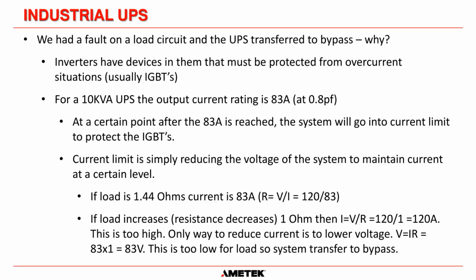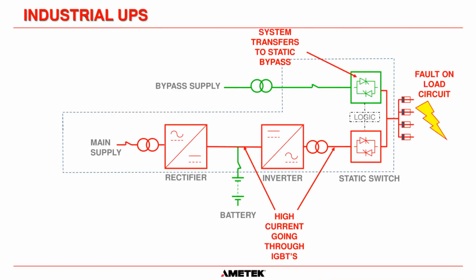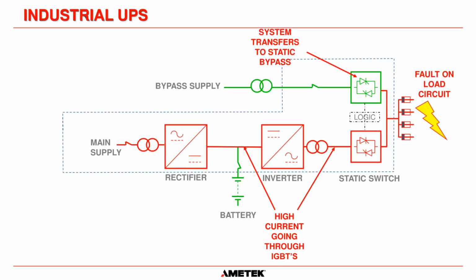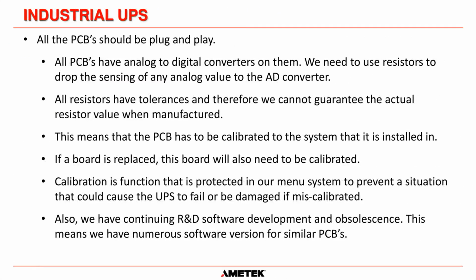So it will do everything it can to stay on inverter and keep the voltage up. But when Ohm's law says it has to go past, let's say, 100 volts AC, the system is going to say, that's too low for my loads, I'm going to transfer to bypass. And that's basically showing you at block diagram level what happens. If there is too high a current going through the IGBTs, then the system is going to transfer to bypass, and then the bypass will clear the loads. The bypass has a huge amount of power behind it, and it will trip the load if necessary to clear that fault. And then if the system has auto retransfer turned on, it will switch back to inverter once that fault has cleared. Oh, we still have one more.